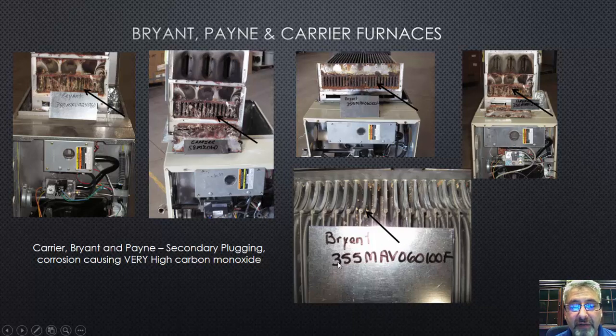So if you look at the Bryant 355 MAV060, 9 out of 10 technicians, if they don't know the nomenclature, are going to say, oh, it's a 60,000. No, it's not. In the Bryant, the 60 right here represents its blower capacity. And for those of you Rapid Tech students, you know that 12,000 BTUs, okay, 60 represents what? 5 tons, right? So that's a 5-ton blower drive. That's all it means. This is your BTUs right here, 100. All right, so a little bonus.